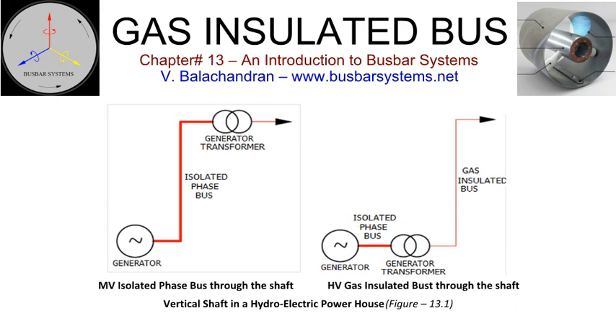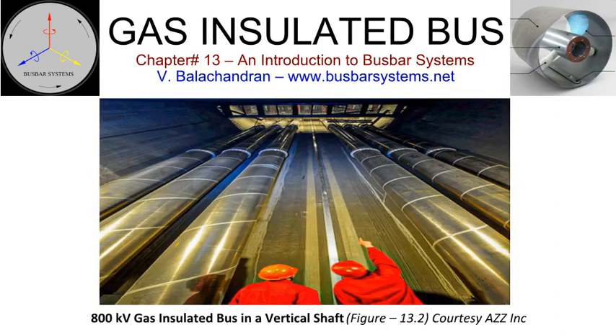The gas-insulated bus generates fewer heat losses, does not require maintenance, and the cross-section area of the shaft will be less. Gas-insulated bus will weigh far less than an isolated phase bus for carrying the same power for obvious reasons. A hydroelectric power station has a vertical gas-insulated bus of 300 meters, 1,000 feet, suspended from the top. A techno-commercial analysis can establish the selection of any one of the two alternatives.